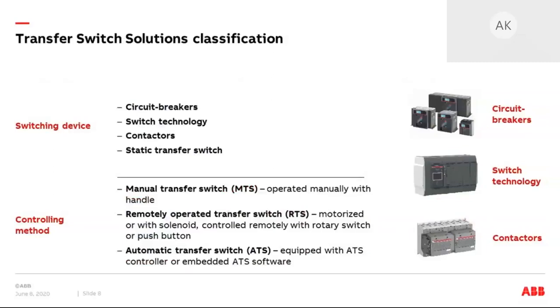Transfer switches can also be differentiated by controlling method. There are manual transfer switches operated with a handle, with an operator standing in front of the switchgear. Remotely operated transfer switches are usually equipped with an electrical motor or solenoid, though the presence of an operator is still required to initiate the transfer. The most common controlling method is automatic — automatic transfer switches are usually remotely operated equipment with an external ATS controller or embedded ATS software.